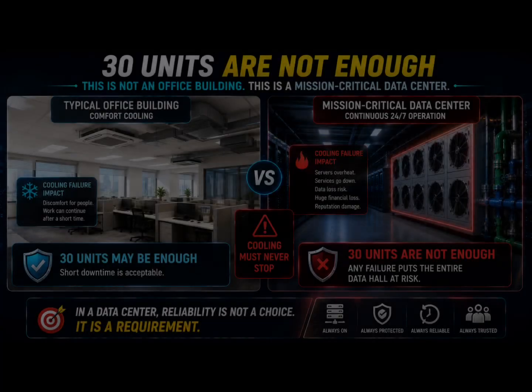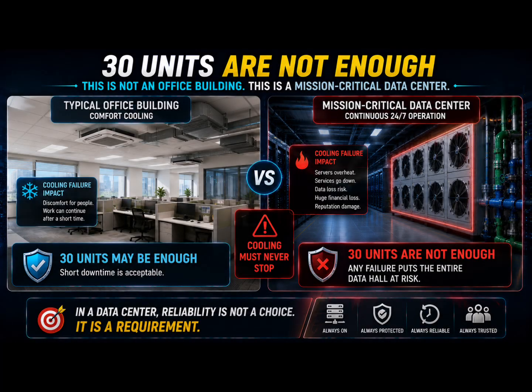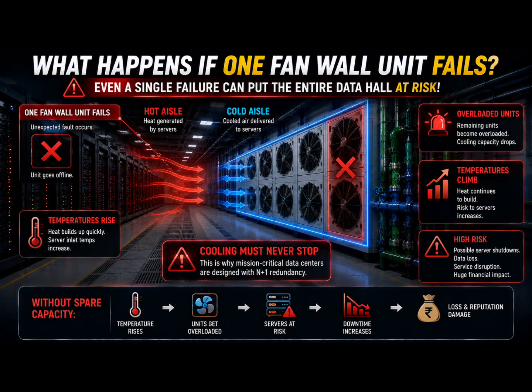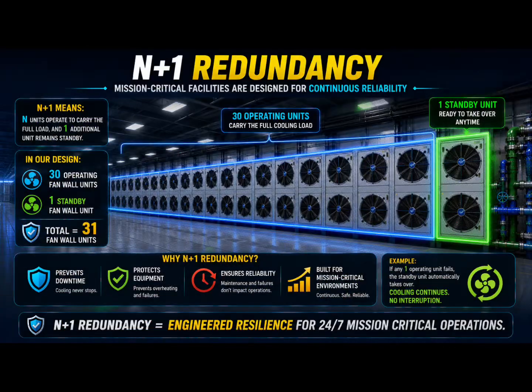But this isn't an office building. This is a mission-critical data center. Cooling must never stop. Imagine one fan wall unit unexpectedly fails. Without spare capacity, the remaining units would immediately become overloaded. Temperatures would begin rising, and the risk to the servers would increase. That's why mission-critical facilities are designed using N+1 redundancy.